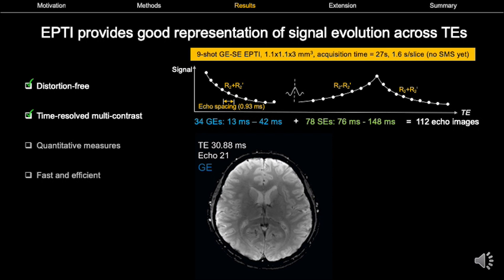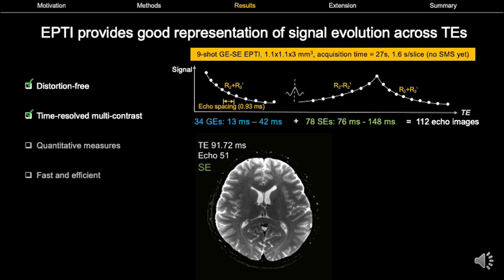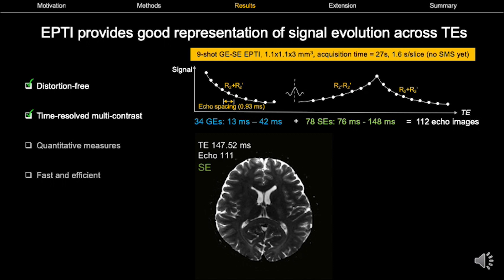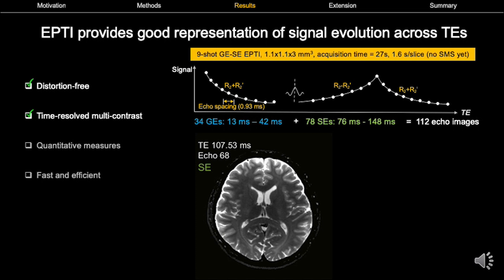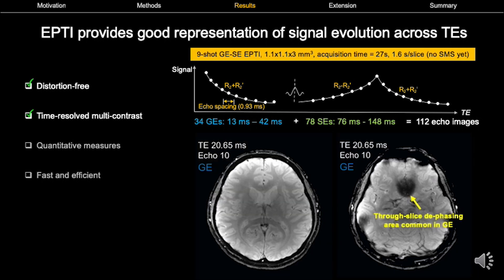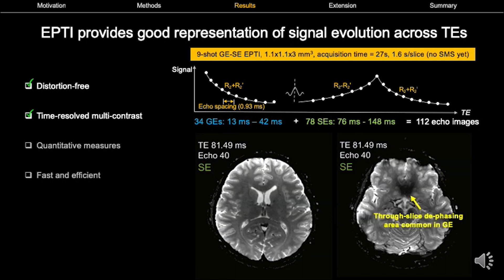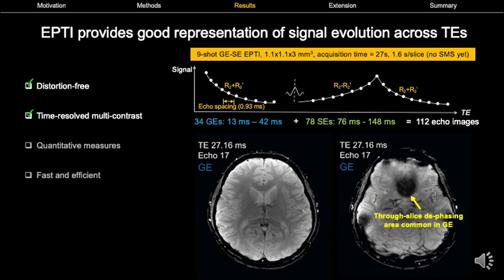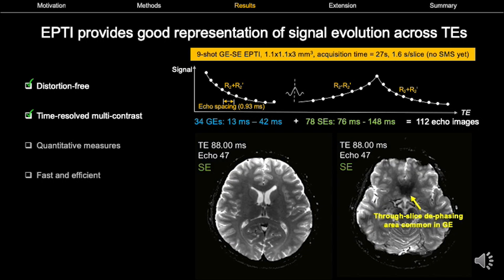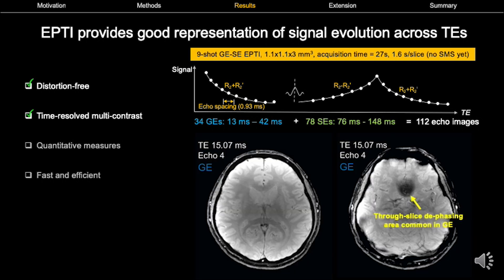To show the time-resolving capability of EPTI, we acquired data using a nine-shot gradient and spin echo EPTI at 1.1 mm in-plane resolution within 27 seconds. This gives us 112 images including both gradient and spin echo, providing signal evolution information at different echo times as seen in the movie. Looking at a lower slice at the bottom of the brain where there are usually more distortions, EPTI still works well and gives distortion-free images. Signal changes in through-slice dephasing areas in gradient echo show an accurate representation of the signal across gradient and spin echo time points.